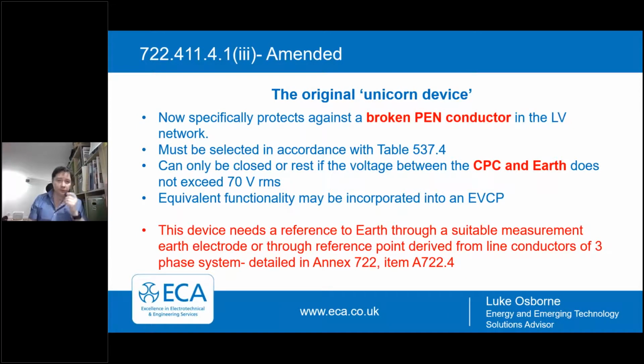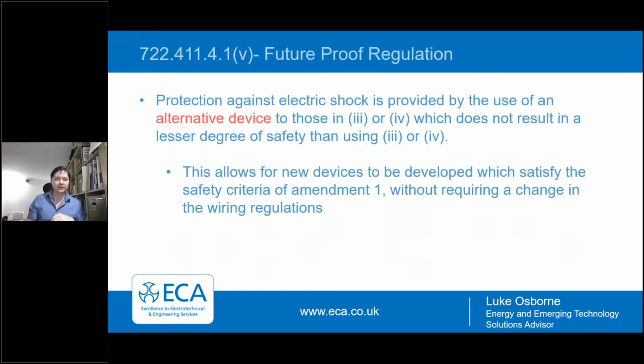I mentioned the original Unicorn device. The text has been amended just to say that it's specifically there to protect against a broken PEN conductor. So I won't labour on that point. And there is also a future-proof regulation, indent 5. So this now allows you to offer protection against electric shock provided by the use of an alternative device to those in the other indents that doesn't result in any less degree of safety than those. And this allows industry to develop new devices which will conform, which will provide an element of safety without the need for changing the text in 722 or requiring another amendment.